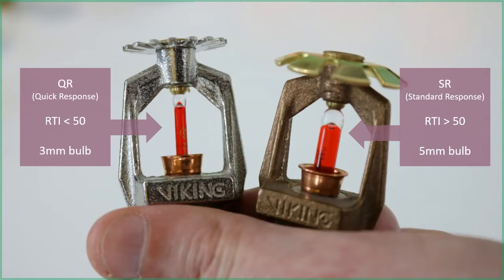So I just wanted to start off by reminding you about the quick response and the standard response bulbs. The main difference is the thickness of the bulb. The standard response has an RTI greater than 50, and that is a response time index. It doesn't mean 50 seconds.